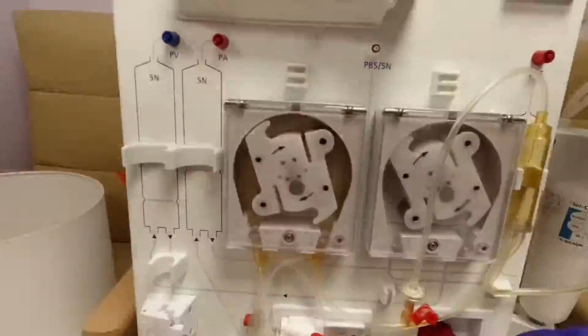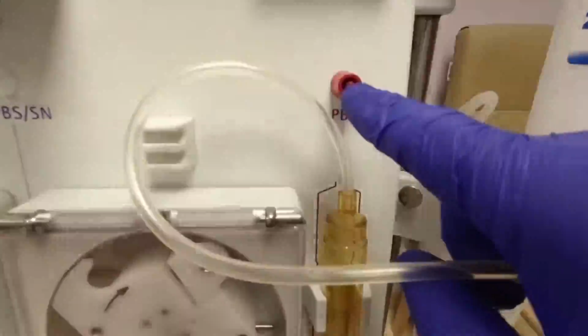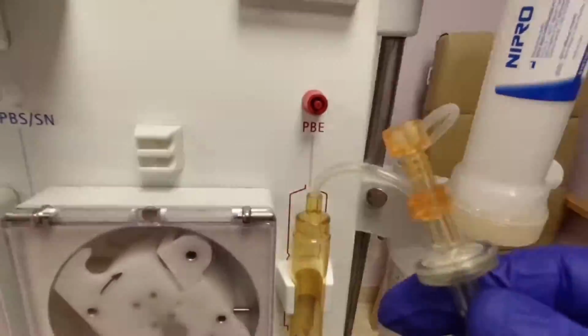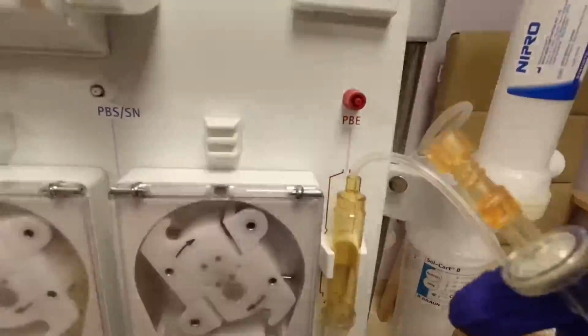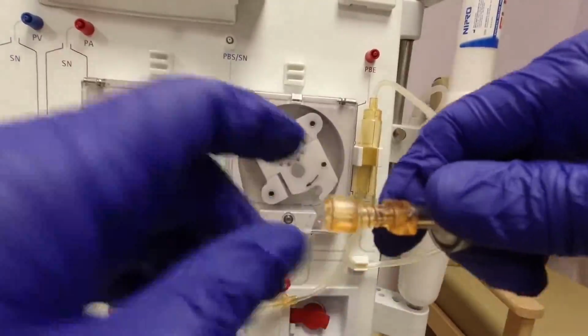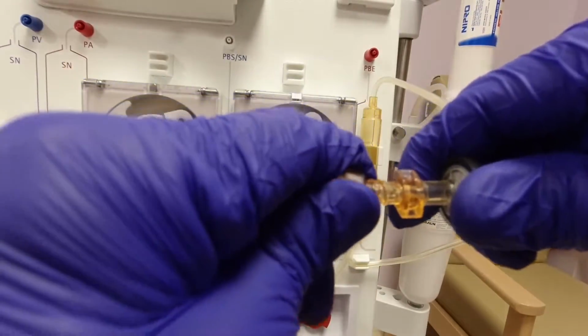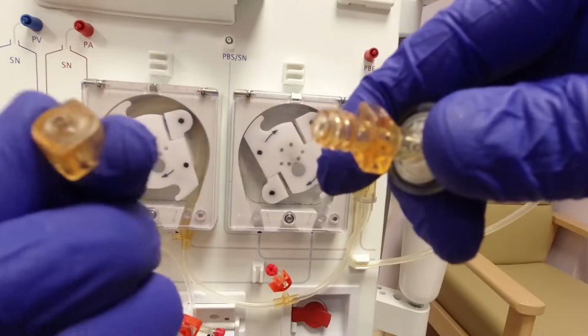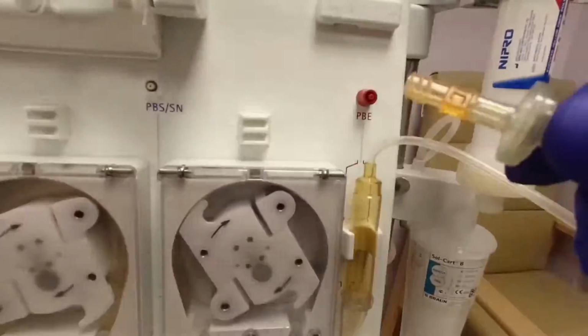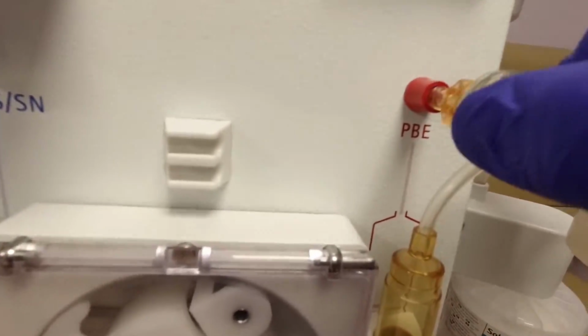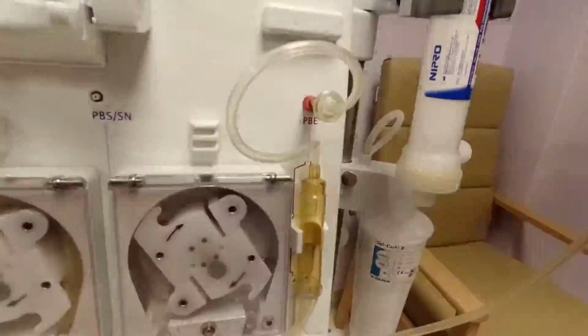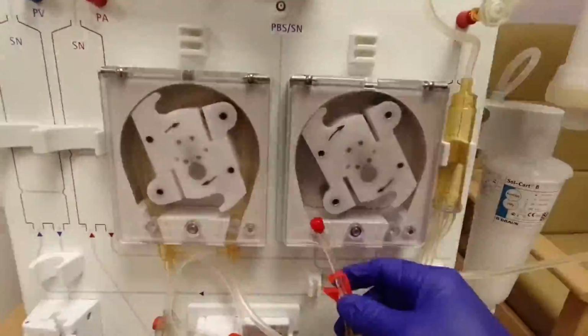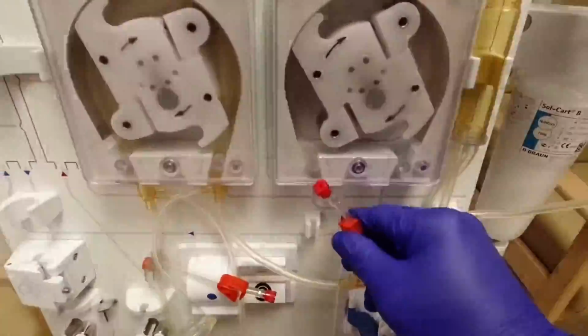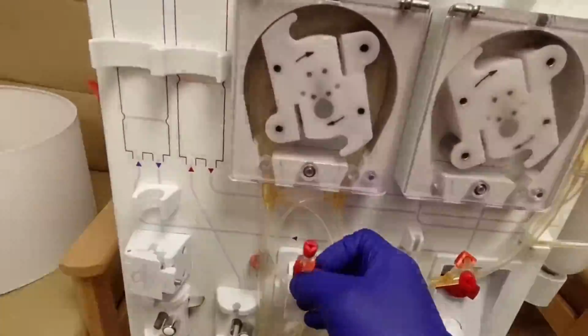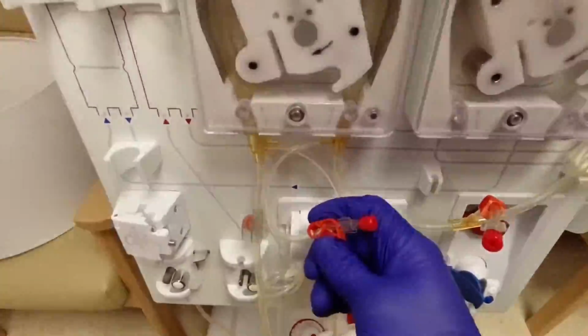Now, going back to the lines. We've got a chamber there, and you can see we've got a pressure port in there. This bit is where it's going to go. So we're just going to take this off. Take that bit off. There you are, and that's going to go there. That's your pressure transducer in there. All the loose ones we're just going to clamp. I believe in clamping all the lines to make sure there will be no blood leak later on.